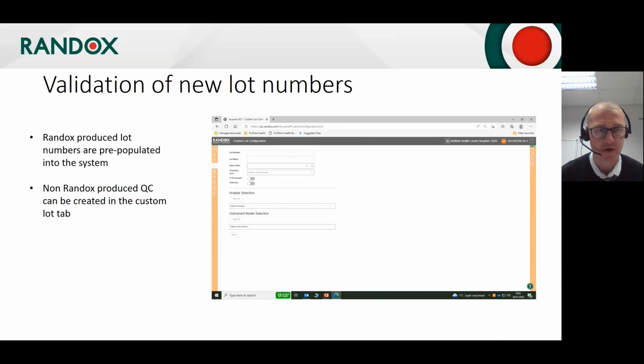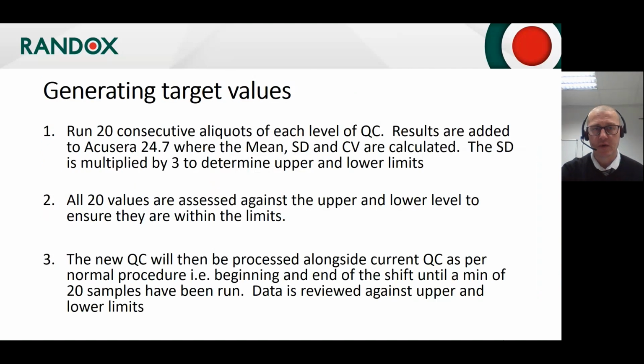The non-Randox QC, which we don't use much of, to be honest, you can create these in the custom lot tab, whereby you enter your lot number, your lot name, expiry date, your type, and then you pick your analytes and your instrument, save it, and then it just needs mapping, and everything goes across as it should. So as I said, we generate our own target values.